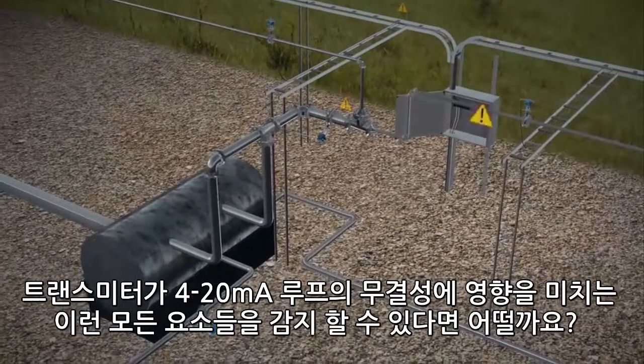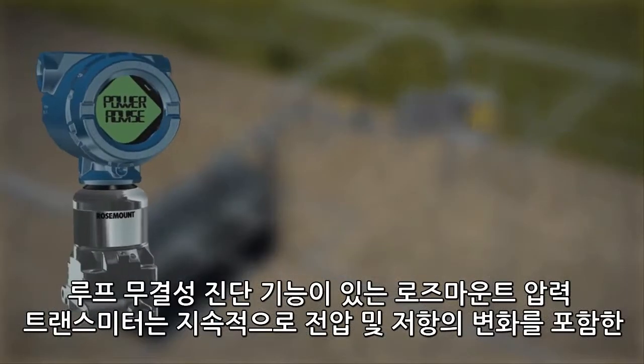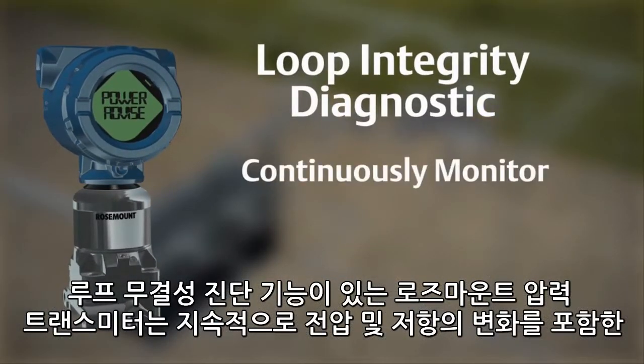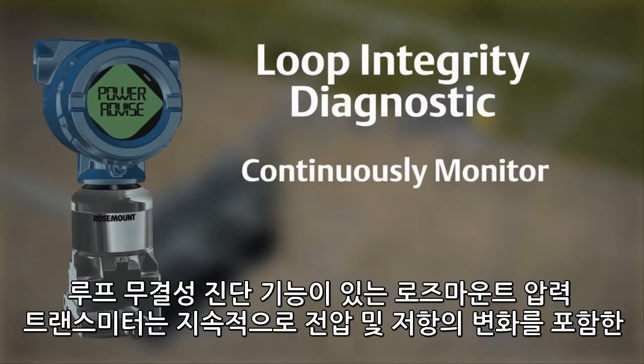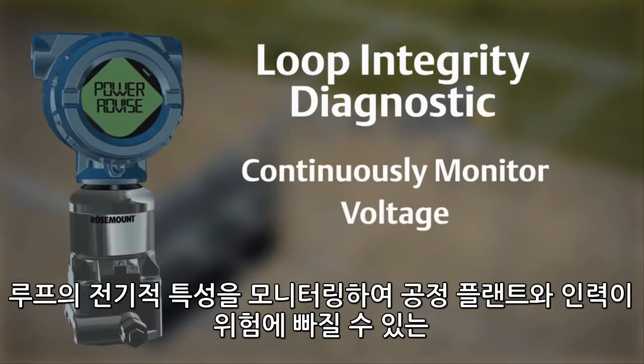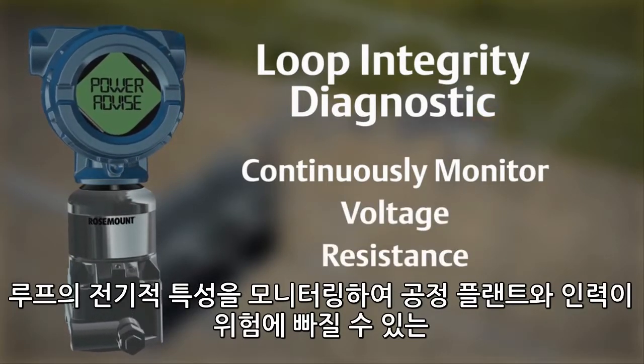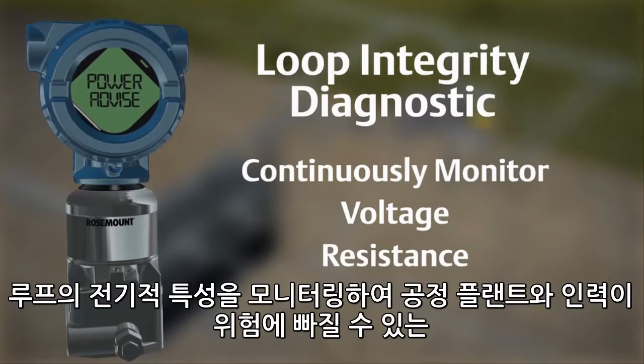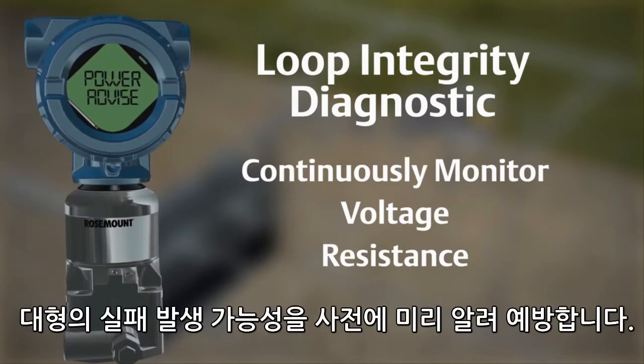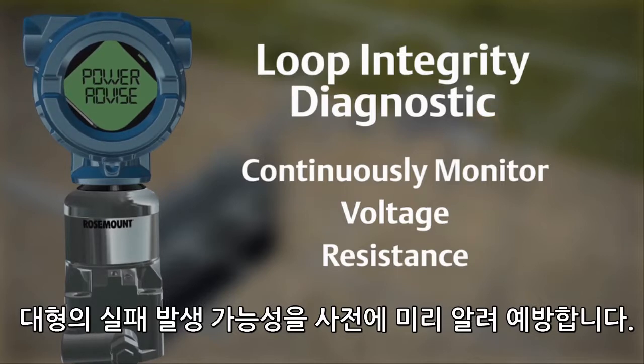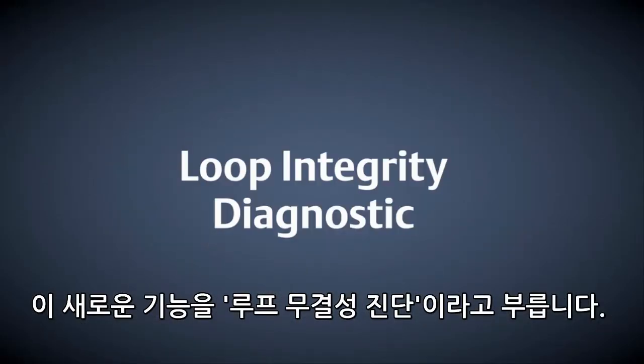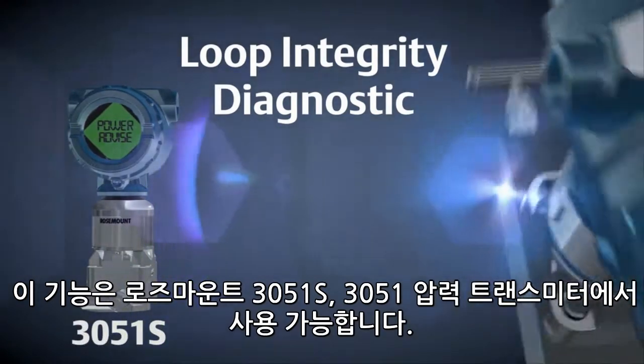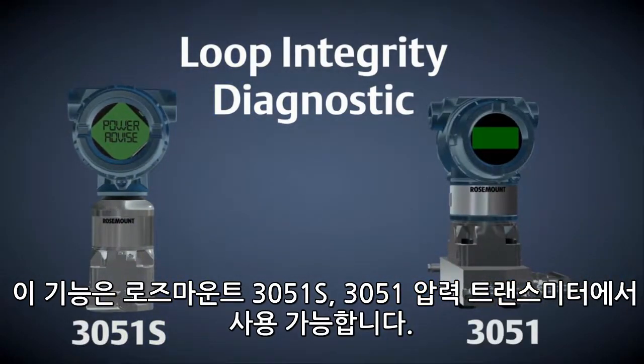Rosemount pressure transmitters with loop integrity diagnostics continuously monitor the electrical characteristics of the loop, including changes to the voltage and resistance, allowing you to be alerted to these conditions before they can cause an on-scale failure that may put your process, plant, and people at risk. This new capability is called Loop Integrity Diagnostics. It is available on Rosemount 3051S and 3051 pressure transmitters.